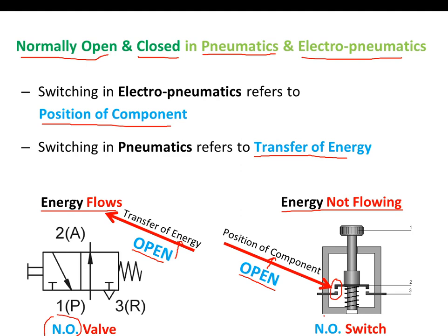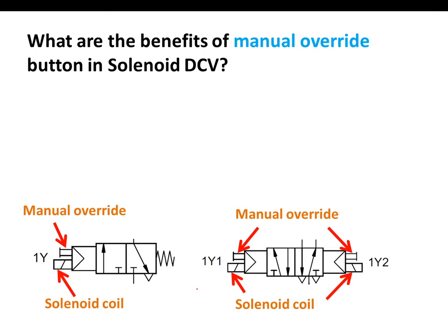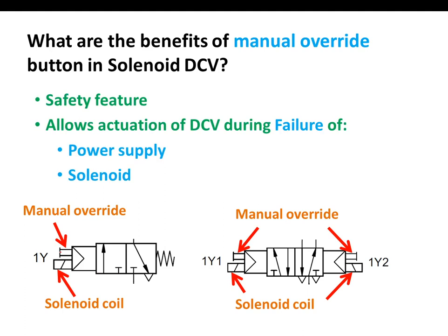What are the benefits of manual override? When we talk about DCVs in electro-pneumatics, they are solenoid driven, and most designs come with a manual override. A manual override is a safety feature that allows actuation of the DCV even during failure — either failure of the power supply or failure of the solenoid itself. When the solenoid fails, we can still actuate manually using this manual override.